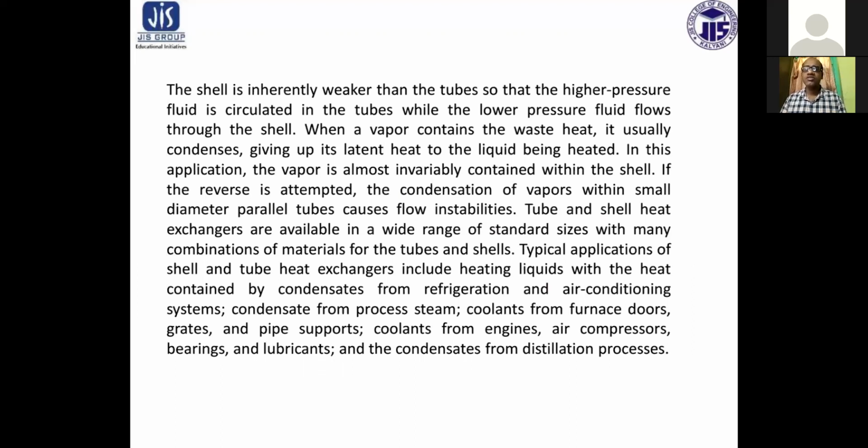So in this type of heat exchanger, the fluid flowing inside the tubes is at higher pressure, and the fluid that contains more energy, that is the wasted energy that we need to recover, whether in terms of liquids or vapor, is at lower pressure and flows over the tubes of the heat exchanger.